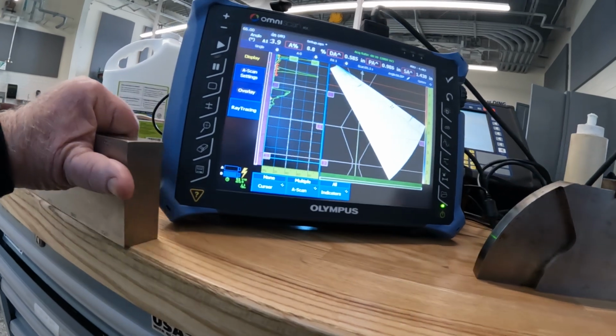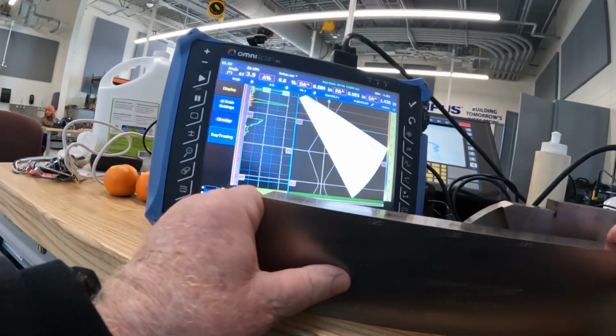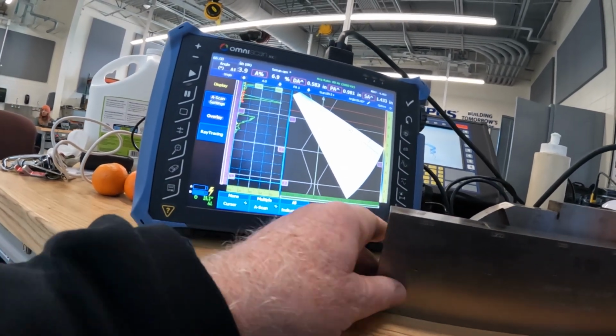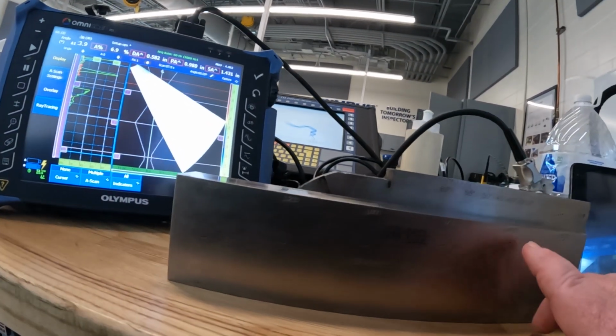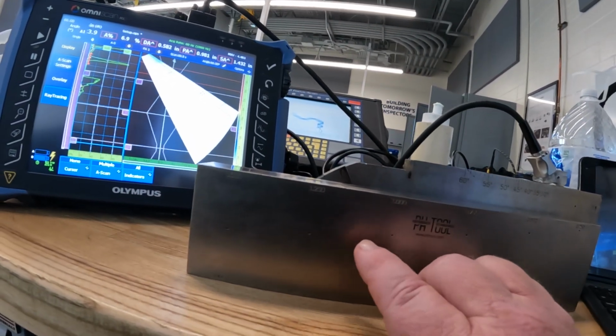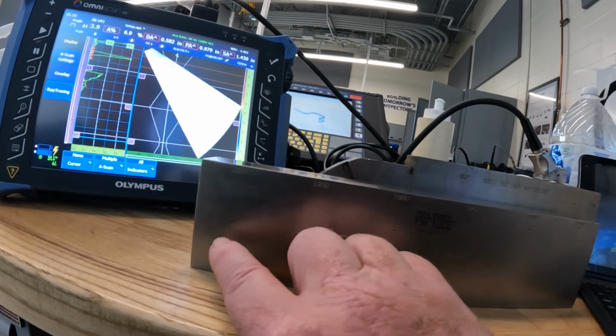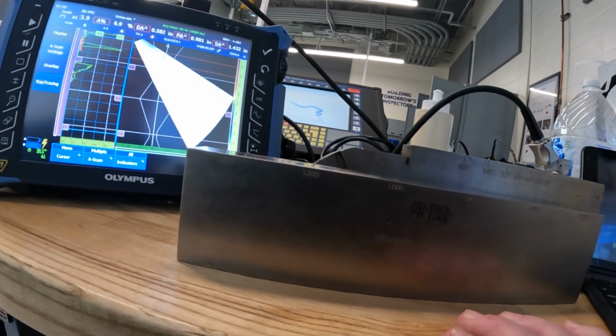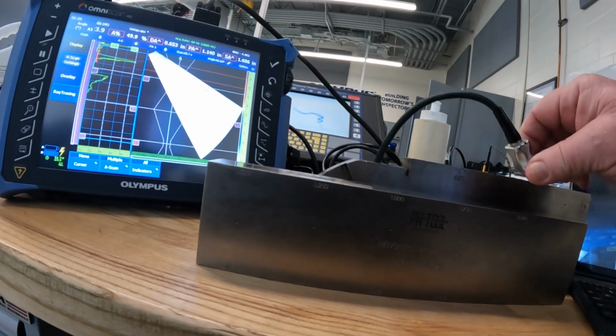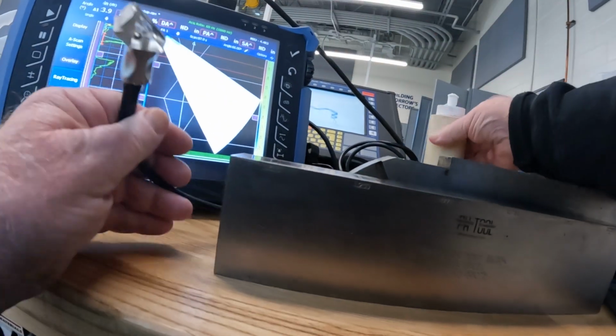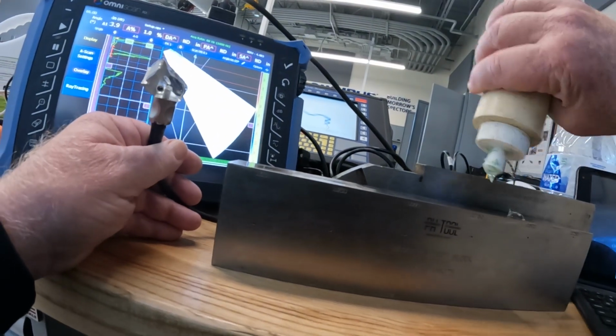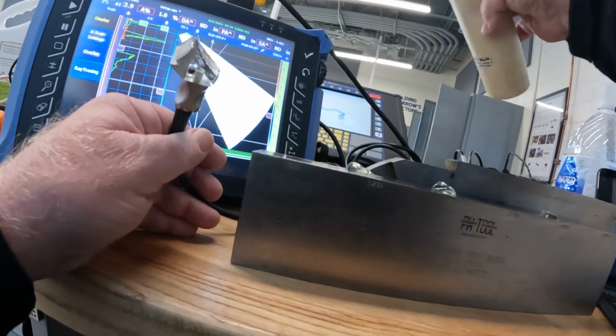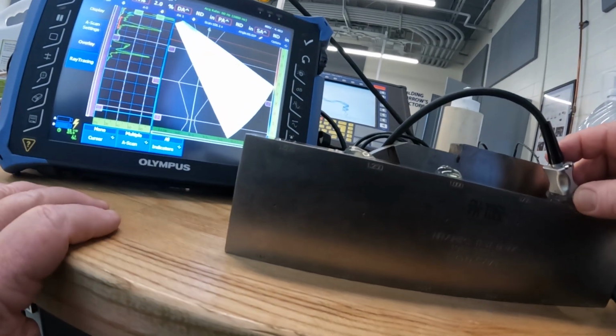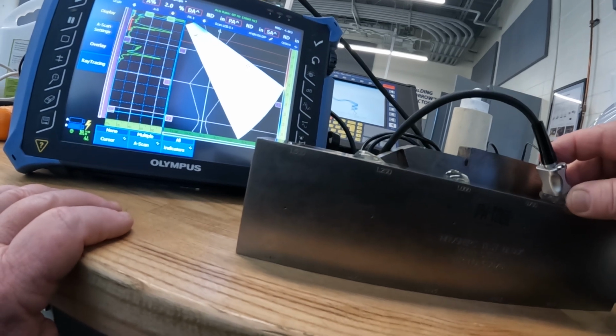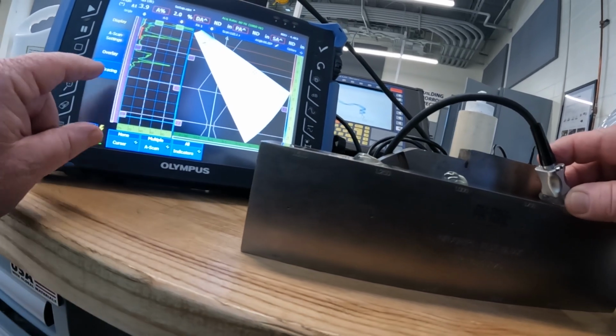So for TGC on this, we're going to use the NAVSHIPS block. We're going to use the 1/2 inch, the 1 inch hole, and the 1.5 hole. And so we're already pointing it at the, I'm going to switch over to a 1/2 inch reflector, put my couplant on. And here we go. So to do TGC, it's like doing sensitivity multiple times. So you see my hole there?